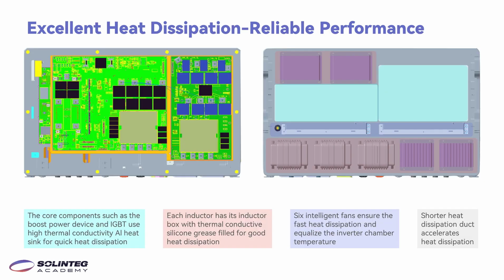This part introduces the inverter's excellent heat dissipation. The inverter has a horizontal design, so compared with a vertical design, the heat dissipation channel is shorter, which accelerates the heat dissipation. Also, it has 6 intelligent fans to ensure fast heat dissipation. For the core components such as the boost power device and IGBT, we use a high thermal conductivity aluminum heat sink. And each inductor has its inductor box with thermoconductive silicone grease. The excellent heat dissipation ensures the reliability and long life performance of the components.